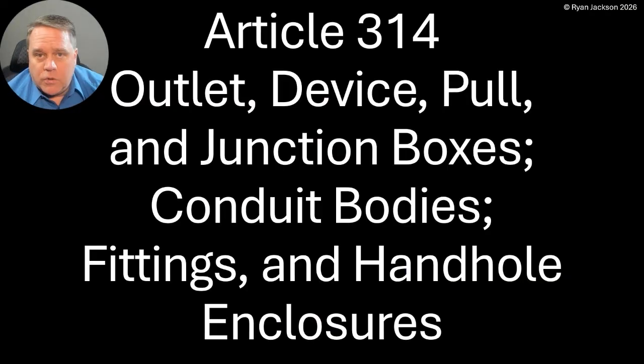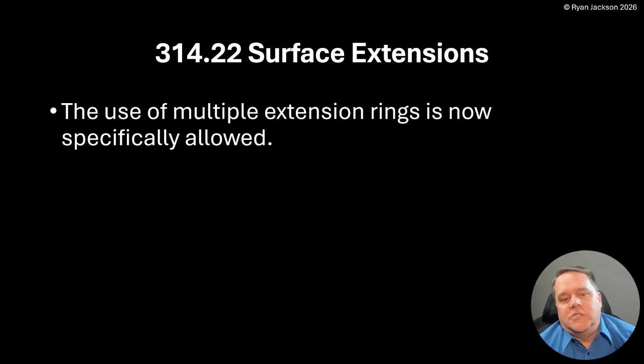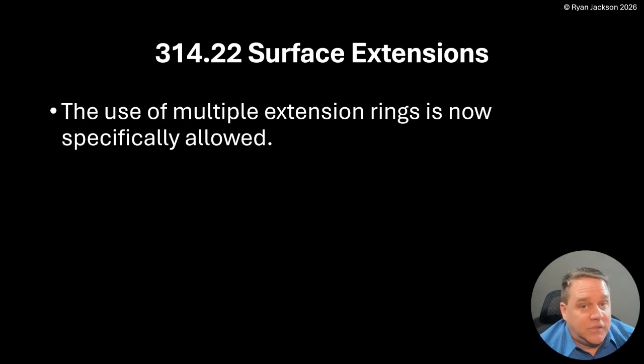They made a really nice clarification here. Truth be told, the rule is the same with or without the additions in the 2026, but it will reduce conflict and arguments in the field, and that's always worth doing. So let's take a look. Article 314 — outlet, device, pull, and junction boxes, conduit bodies, fittings, and handhole enclosures. Section 314.22: Surface Extensions. The use of multiple extension rings is now specifically allowed.